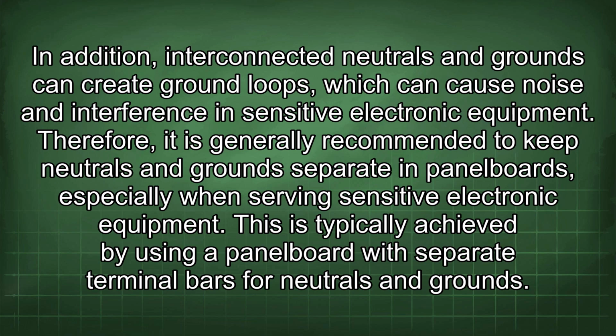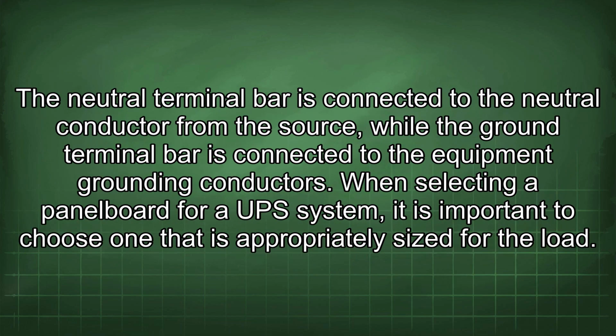equipment. Therefore, it is generally recommended to keep neutrals and grounds separate in panel boards, especially when serving sensitive electronic equipment. This is typically achieved by using a panel board with separate terminal bars for neutrals and grounds. The neutral terminal bar is connected to the neutral conductor from the source, while the ground terminal bar is connected to the equipment grounding conductors.